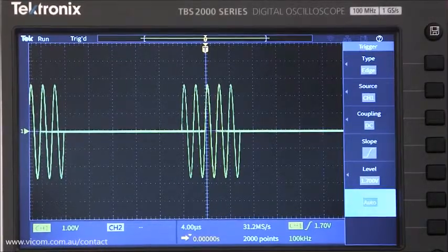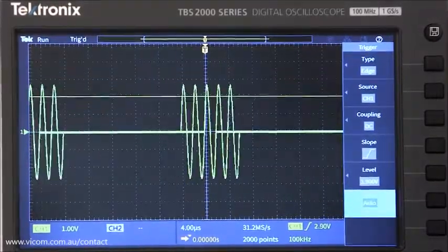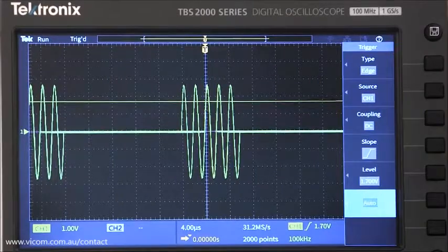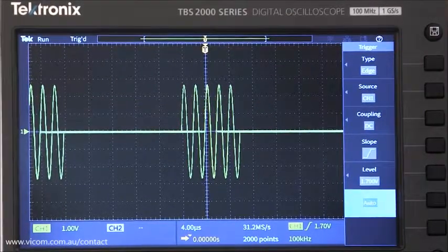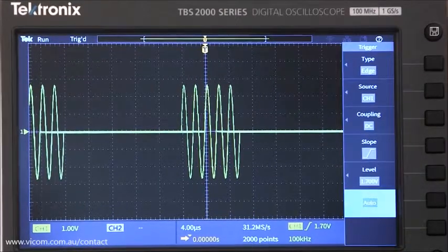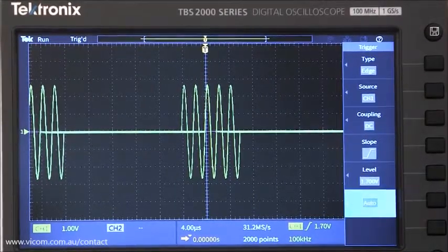In this mode, the scope waits for a trigger, and if it doesn't see one, it captures and displays a waveform even if the trigger conditions aren't being met. Auto mode shows waveforms that aren't synchronized, but it's really useful for setting up the trigger. For signals that meet the trigger conditions pretty often, auto mode will give you a stable trigger.